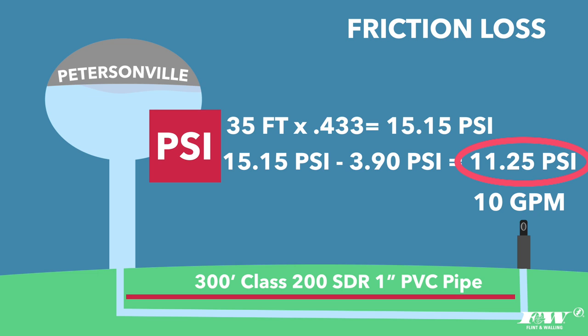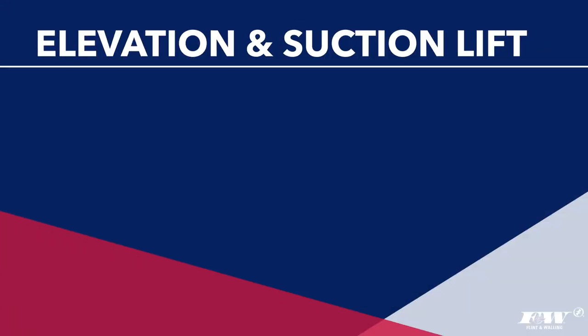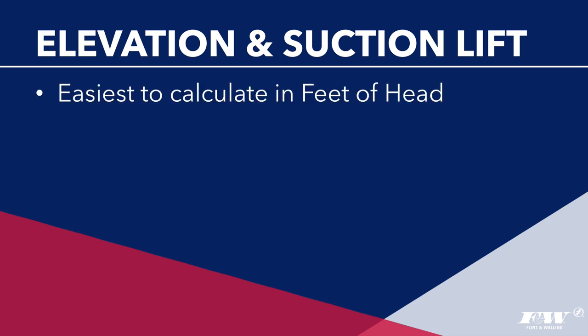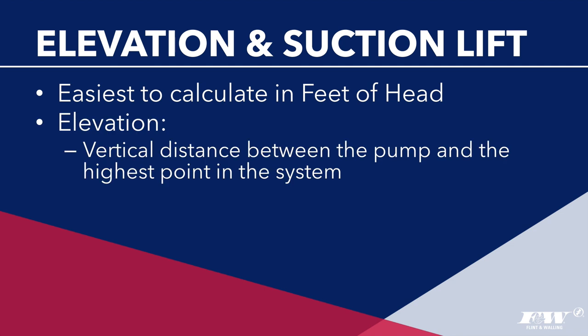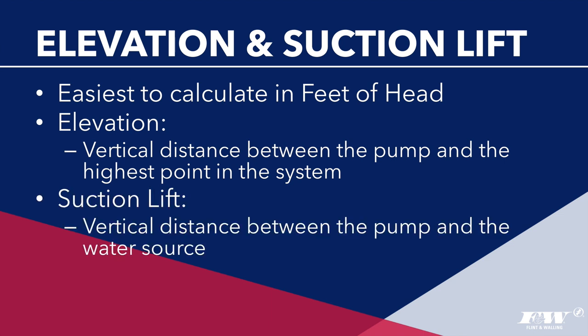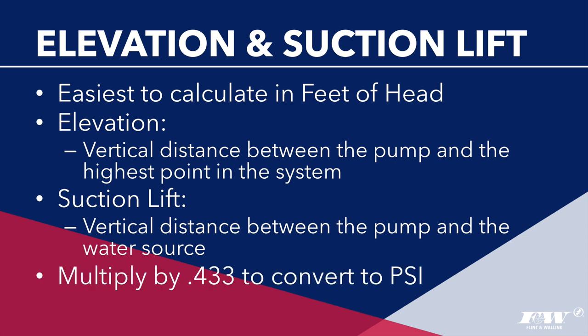There are two additional terms that come up when sizing a pump: elevation and suction lift — both easiest to calculate in feet of head. Elevation is the vertical distance between the pump and the highest point in the irrigation system; the number of feet of vertical distance equals the feet of head of pressure difference between those two points. Suction lift is the vertical distance between the pump and the water source it draws from, used when sizing a centrifugal pump drawing from a well, lake, pond, or stream. To convert to PSI, multiply feet of head by 0.433.